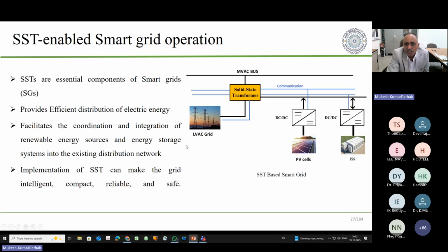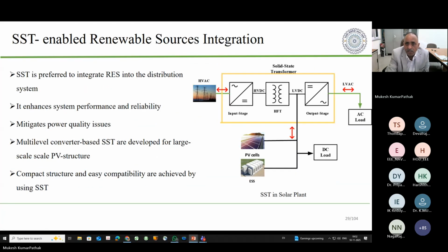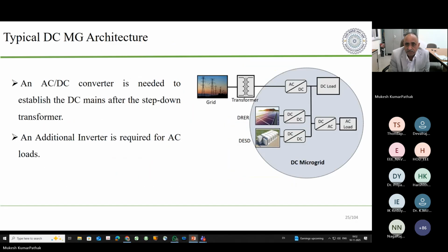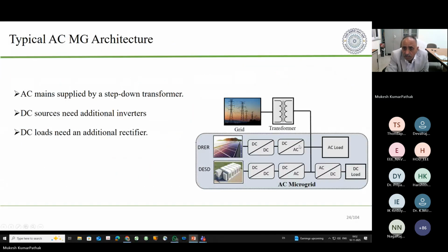With a solid state transformer, you have a direct connection to the grid. You can directly connect these cells through one converter; the next converter is not required. You can convert directly to the output. So in a way, these two converters are not required, since the solid state transformer can handle that. Similarly, this converter would not be required if it's a DC load. If you have both LV and HV, you can use one as per your requirement, and the AC load is directly supplied.